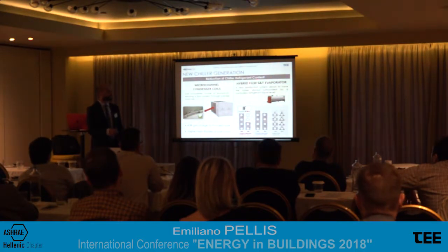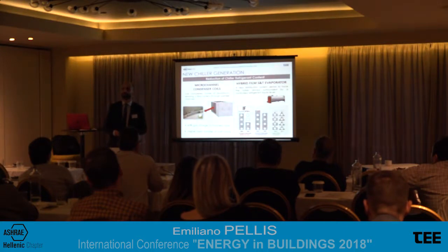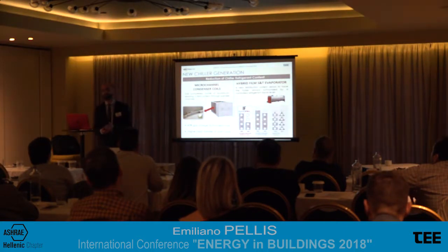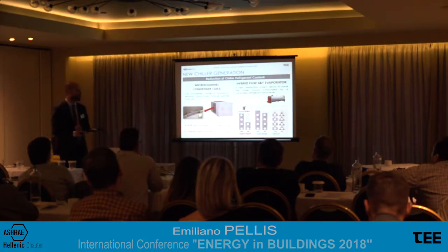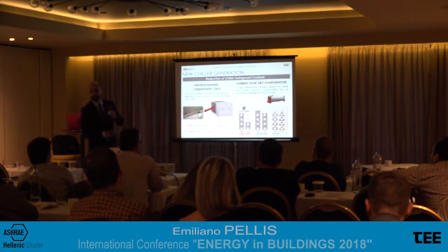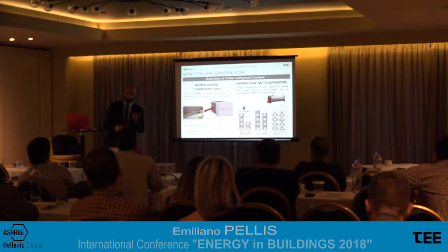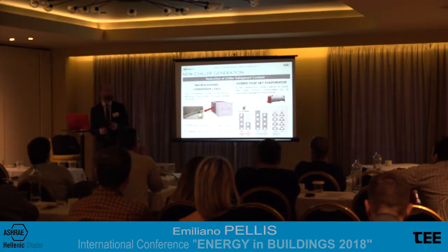The hybrid film shell and tube evaporator. You know, in the market, there is the direct expansion evaporator, and there is also the flooded type, what we call the flooded type evaporator, which is the best one in terms of energy efficiency, because it provides very, very low temperature approaches. But what is the negative point of the flooded type technology? That we need a lot of kilograms, a lot of gas. Indeed, we talk about flooded, okay? So the pipes are flooded by refrigerant.